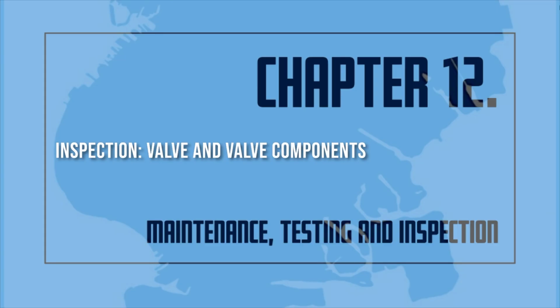D. Valve and valve components. Pre-action/deluge valves. The valve enclosure heating equipment is subject to freezing and shall be inspected daily during cold weather for its ability to maintain a minimum temperature of at least 40 degrees Fahrenheit. Valve enclosures equipped with low temperature alarms shall be inspected weekly during cold weather.